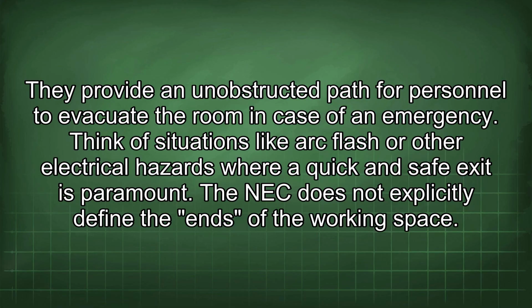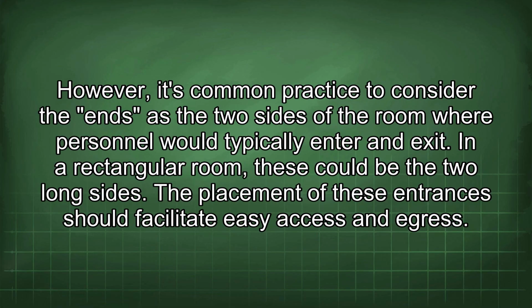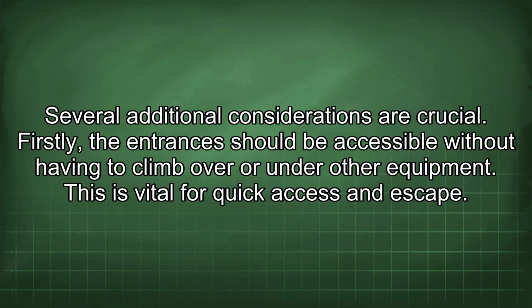The NEC does not explicitly define the ends of the working space. However, it's common practice to consider the ends as the two sides of the room where personnel would typically enter and exit. In a rectangular room, these could be the two long sides. The placement of these entrances should facilitate easy access and egress. Several additional considerations are crucial. Firstly, the entrances should be accessible without having to climb over or under other equipment. This is vital for quick access and escape.